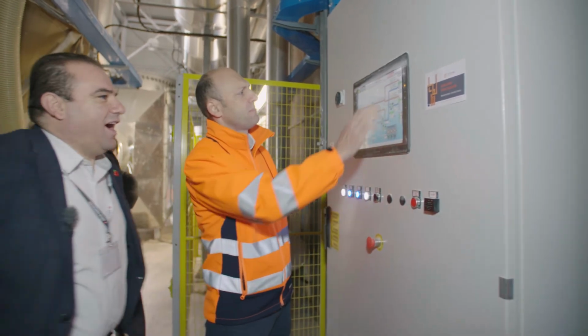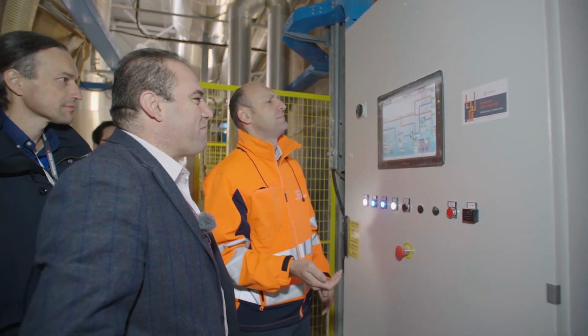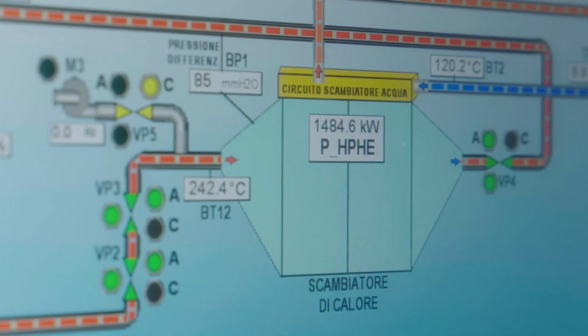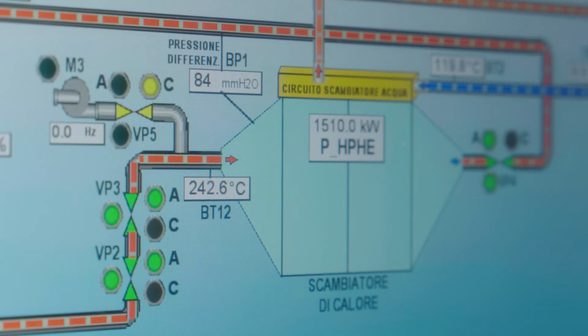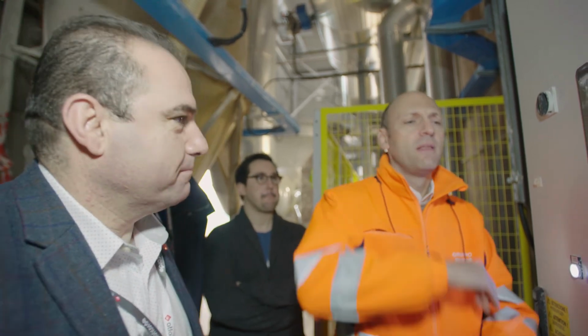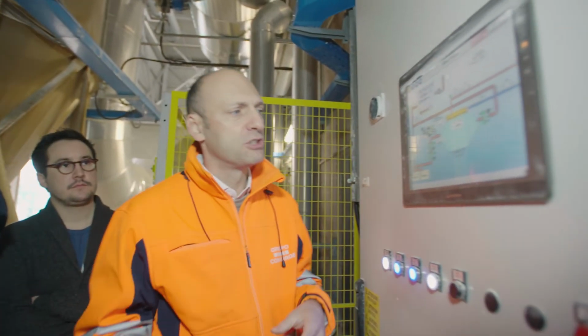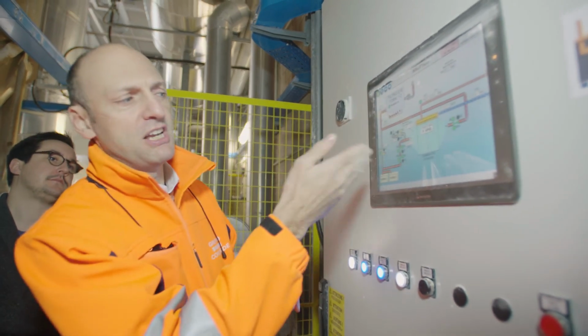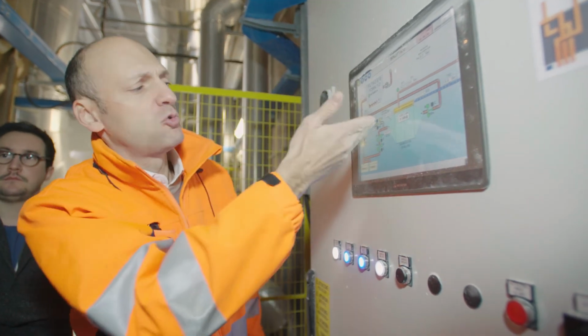The first monitoring data shows that the new heat pipe heat exchanger unit is able to recover thermal energy by more than 40%. This means the investment cost should be recovered within 24 months. Such devices could help the ceramic industry in Europe increase its competitiveness while reducing its environmental impact as well.